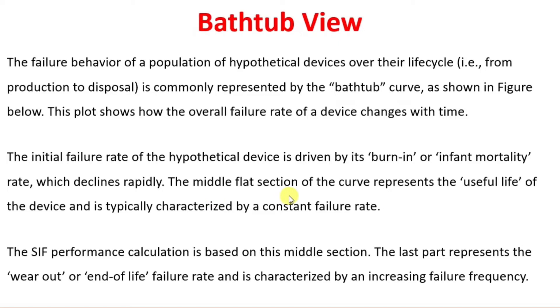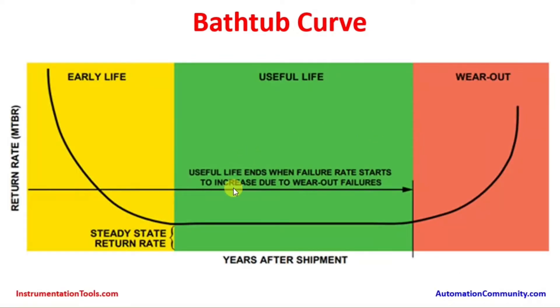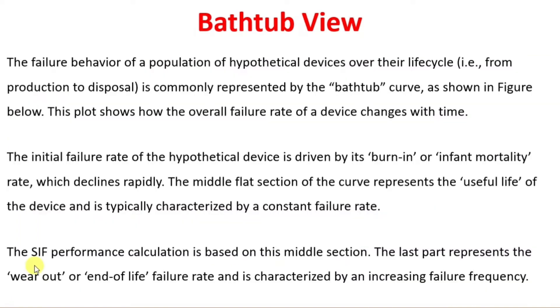The middle flat section of the curve represents the useful life of the device and is typically characterized by a constant failure rate. This middle part, shown in green, represents the useful life, and under normal circumstances the instrument operates healthily over this period with only rare failures. Performance calculations are based on this middle section. The last part represents the wear-out or end-of-life failure rate, characterized by an increasing failure frequency.